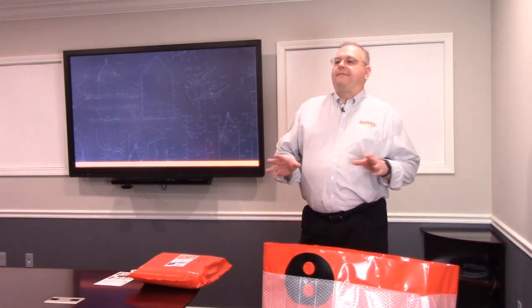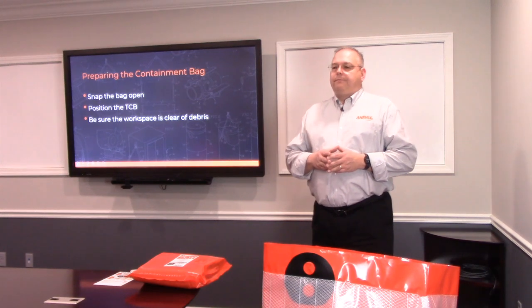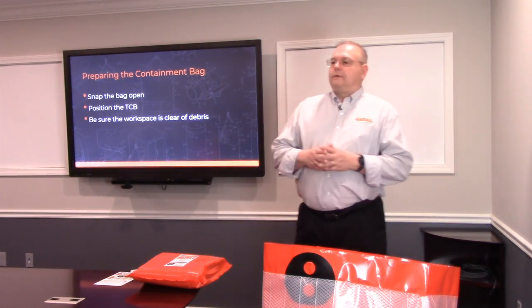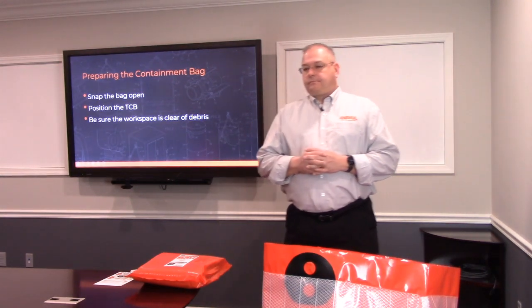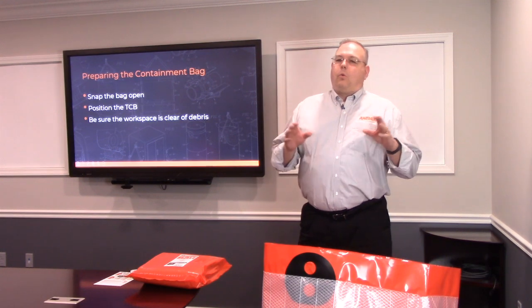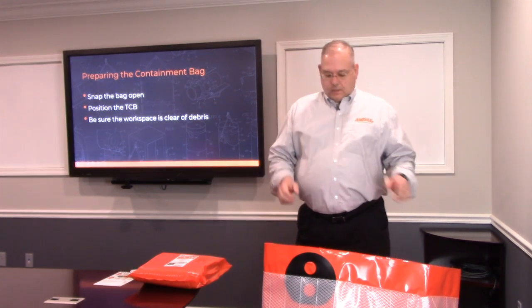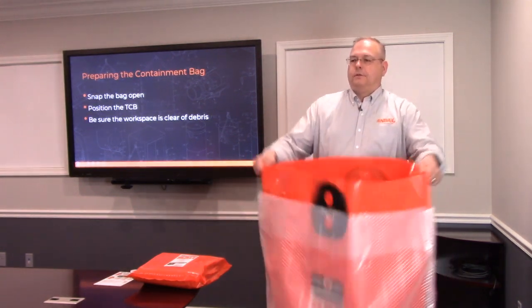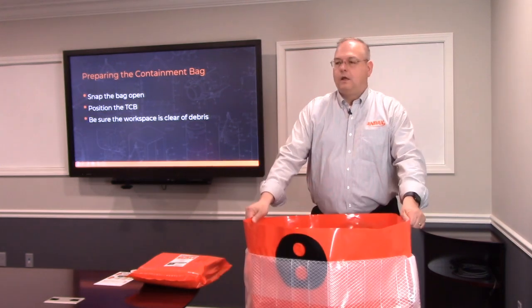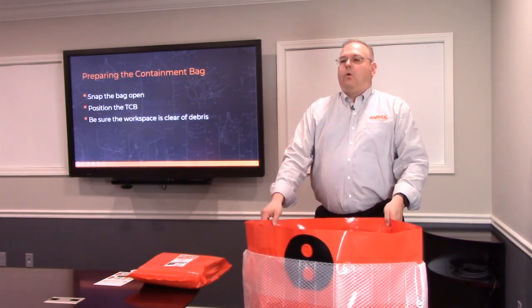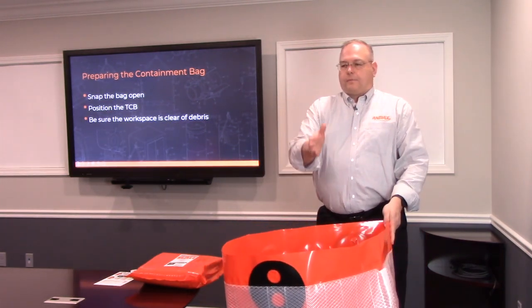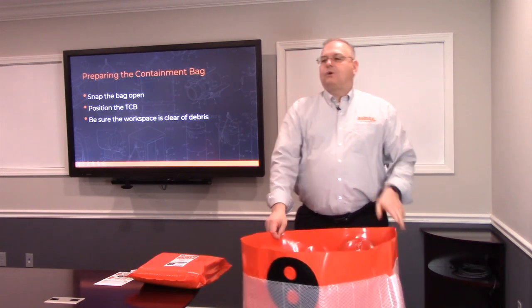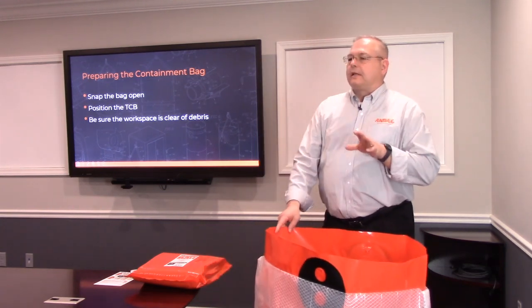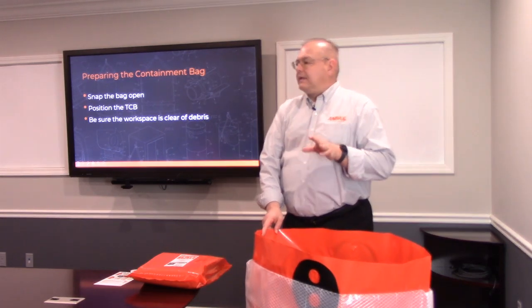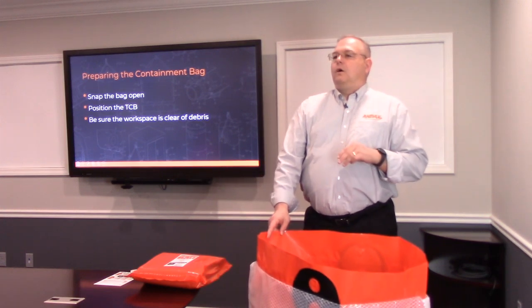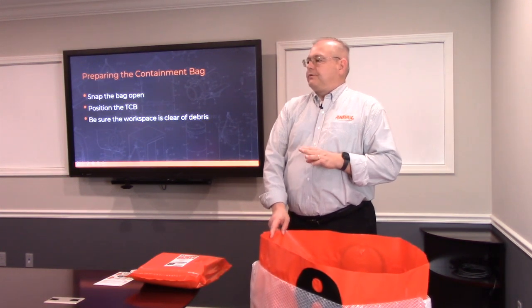Now that we've identified the key features of the TCB, let's discuss how to use it in the field. Once the bag is unfolded, give it a quick snap to straighten it out. Position it where you will be lowering the transformer to the ground. As always, make sure that your workplace is clear of any debris that may end up underneath the transformer, or anything that could be a trip hazard for you and your team.